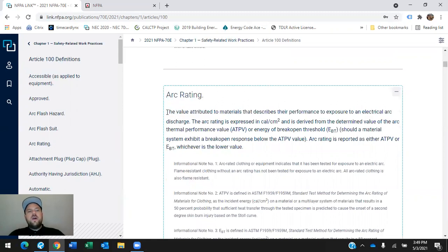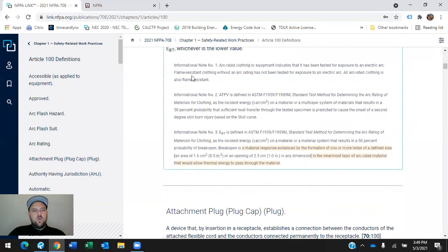An arc rating. This is what I was talking about. You have to have a suit that is rated for whatever the arc rating is of that electrical system. The value attributed to materials that describes their performance to exposure to an electric arc discharge. The arc rating is expressed in cals per centimeter squared and is derived from the determined value of the arc thermal performance, ATPV, or energy of break open threshold, EBT, should a material system exhibit a break open response below the ATPV value. Arc rating is reported as either ATPV or EBT, whichever is the lower value. Again, we have some more informational notes here. We don't need to go into all of those.